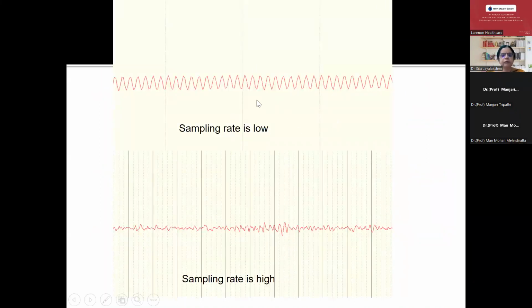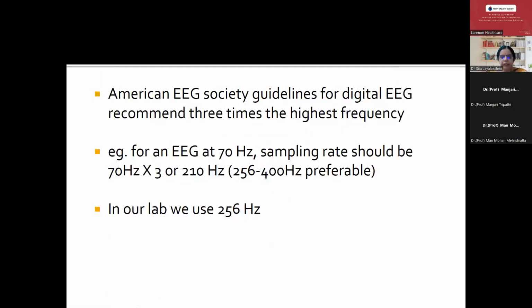This is just to show how the EEG looks when the sampling rate is low, and when the sampling rate is normal, this is the real EEG seen in the lower graph. Finally, the American EEG Society guidelines suggest that for an EEG to be recorded at 70 hertz, the sampling rate should be 3 times the highest frequency, so around 210 hertz. But in most machines nowadays, the digital sampling rate is around 256 hertz, which is reasonably good, because the highest frequency we are recording is 70 hertz.